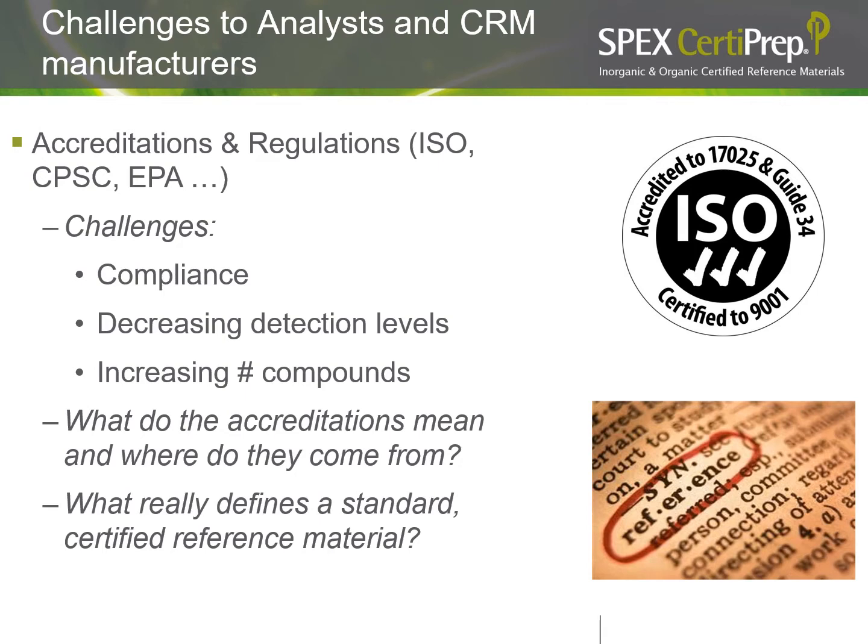So basically class, there are two different terms that I'm going to introduce in this lecture, which is reference material, and another one will be certified reference material. So basically reference material does not meet all the criteria for certified reference materials, whereas for certified reference material, the main principal difference is the addition of evidence of metrological traceability and a statement of measurement uncertainty will be provided on the certificate for CRM. So basically class, more details will be provided on CRM compared to the reference material.